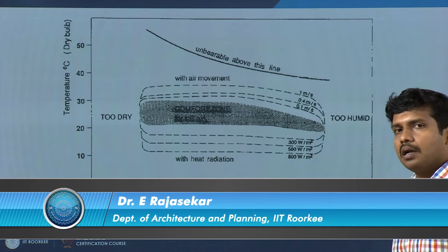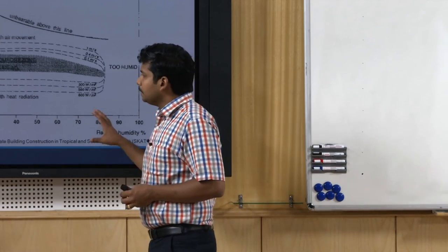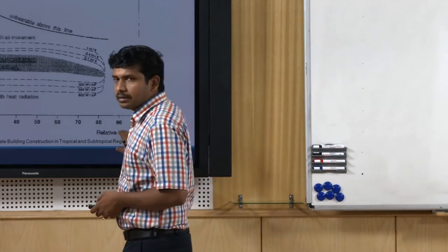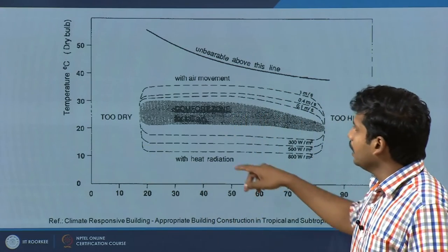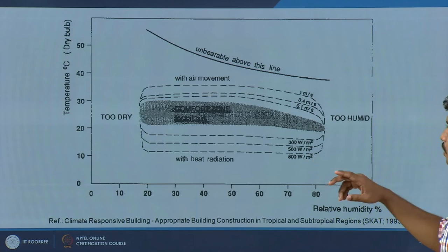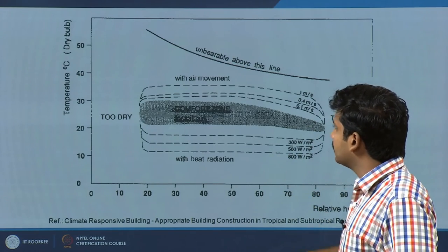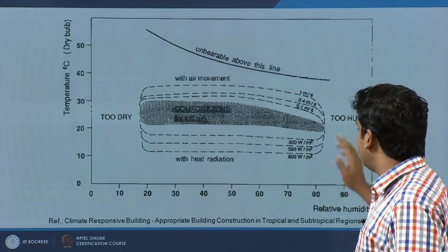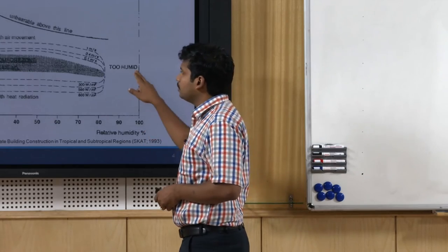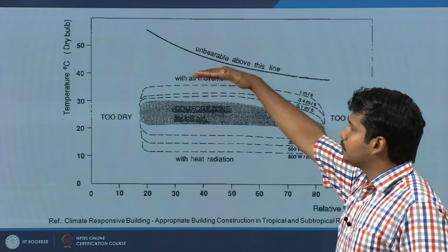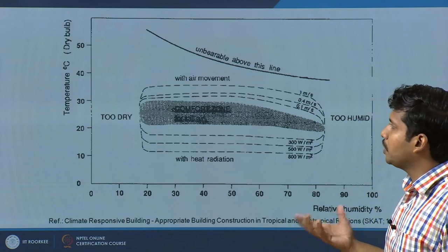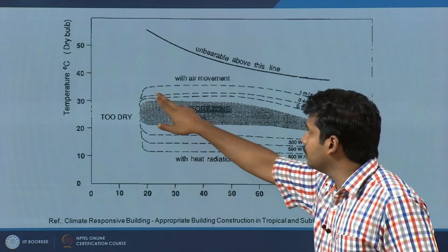The bioclimatic chart is a very interesting chart. It contains relative humidity on its x-axis and dry bulb temperature on the y-axis, with a comfort zone — this zone varies from location to location; originally it was developed in the US. Moving further right means relative humidity is very high — too humid; to the left is too dry. Above the comfort zone, where temperature and humidity are higher, you need better air movement to remain comfortable, which expands the comfort zone shown by the dotted line.